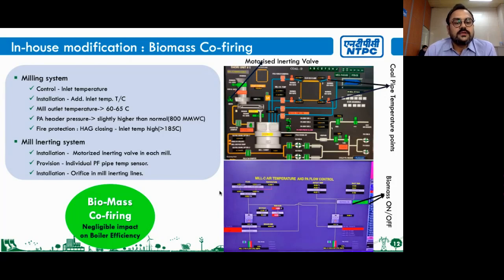Our PA header pressure is maintained at a slightly higher than normal value of 800 mm water column when we fire biomass. And finally, we have changed the fire protection, that is the hot air gate closing at inlet temperature high instead of outlet temperature high.